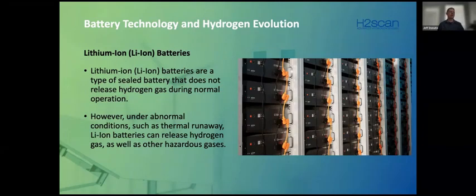So in this case, the primary measure of safety in these batteries is the BMS, the battery management system, which is the brain of the system and monitors the voltage, the temperature, and the current. If anything goes into a fault condition, it will shut the battery down and go into a protection mode. However, if something is not caught or the BMS fails, then it can produce those gases before it actually goes into deflagration. So you're seeing a lot of times in the market that they put gas detection in these sites as a secondary measure for life safety.